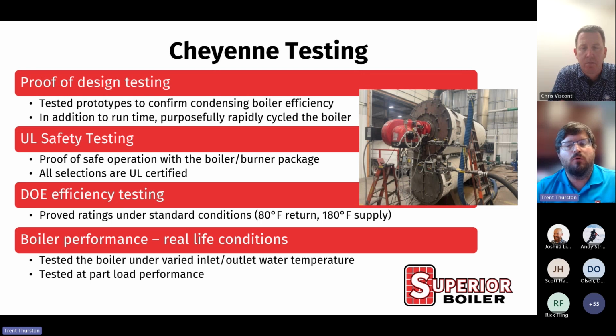Once we completed that, we worked with Underwriters Laboratory, which is a third-party safety certification firm, and this allowed us to prove that the safety controls work correctly on both the boiler and burner package. The next thing we did, witnessed by UL, was the DOE standard rating test, which goes from 80 to 180 at full fire. And what we finally did to give us a full idea of how a boiler will perform at part loads and in real-world conditions is testing at, let's say, 100, 140 at 50% firing rate.